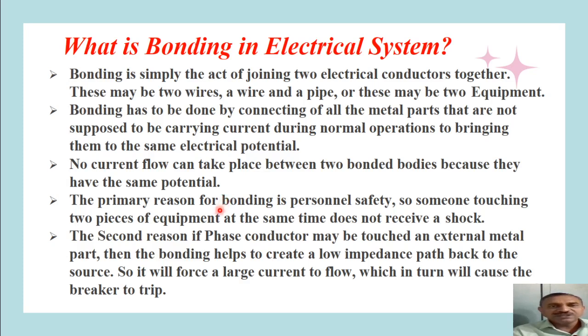Now the primary reason for bonding is the personal safety. If one of that equipment has certain fault and if it is not bonded with another equipment, then the enclosures of that second equipment will carry certain voltage. When a person touches both of the equipment, then he may get a shock. In case of bonding, there is no chance of receiving any shock, as both the equipment body will be at same potential, and that is 0 potential.